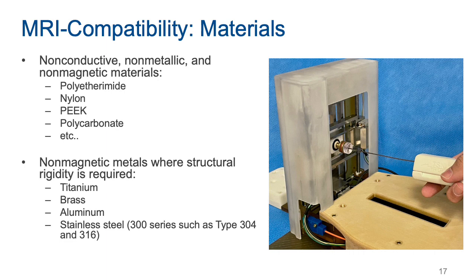However, there are certain areas that need some structural rigidity or precision. Certain non-magnetic metals are also used for MR-conditional robotic devices, such as titanium, brass, aluminum, and certain types of stainless steel. One thing I have to mention here is that some non-magnetic metals, especially stainless steel, can be magnetized after being machined, so it is always important to test every metallic part before assembling them. Otherwise, you may find out that the robot is magnetic after bringing the assembled robot into the bore. And by that time it will be too late to identify the part that is causing the issue.